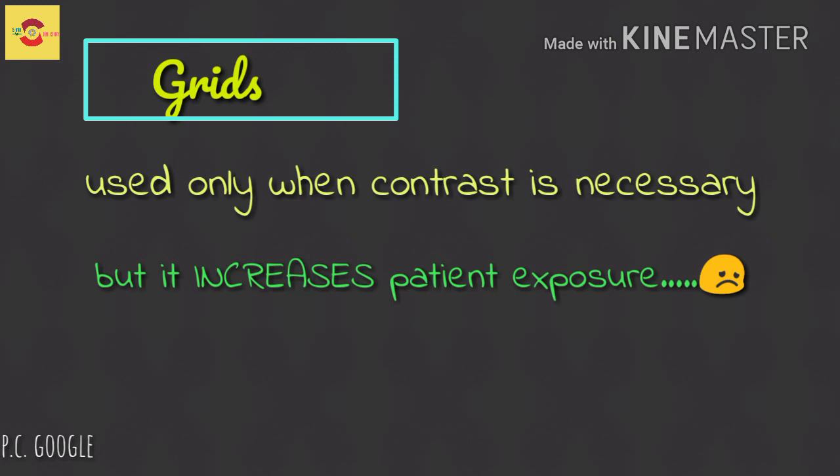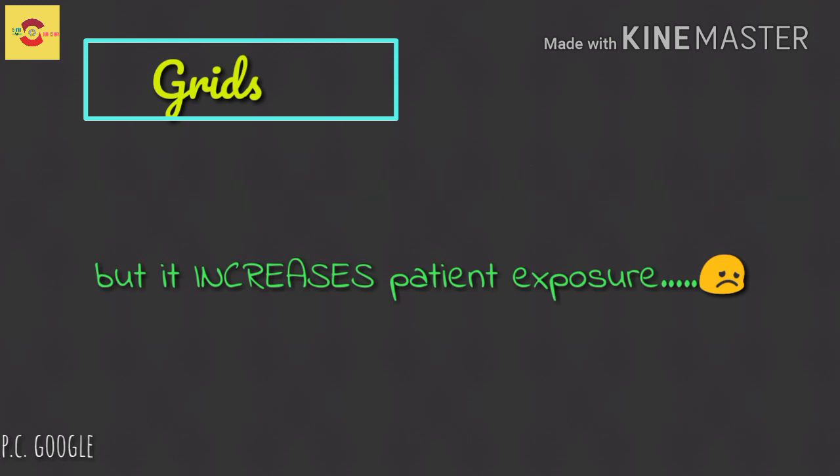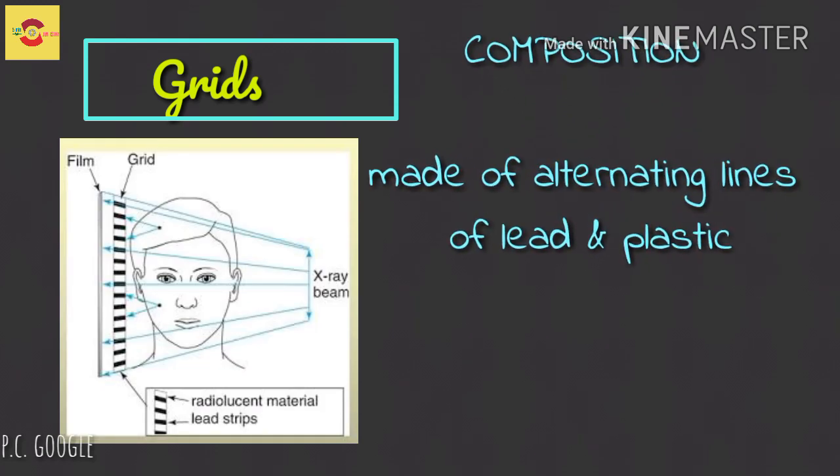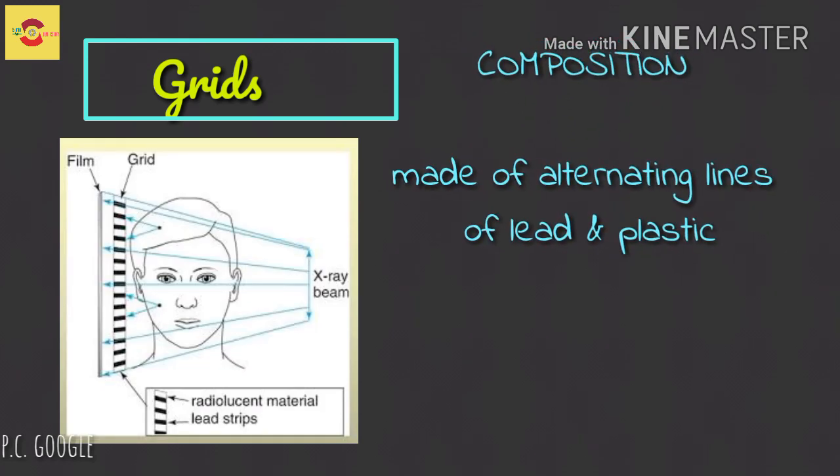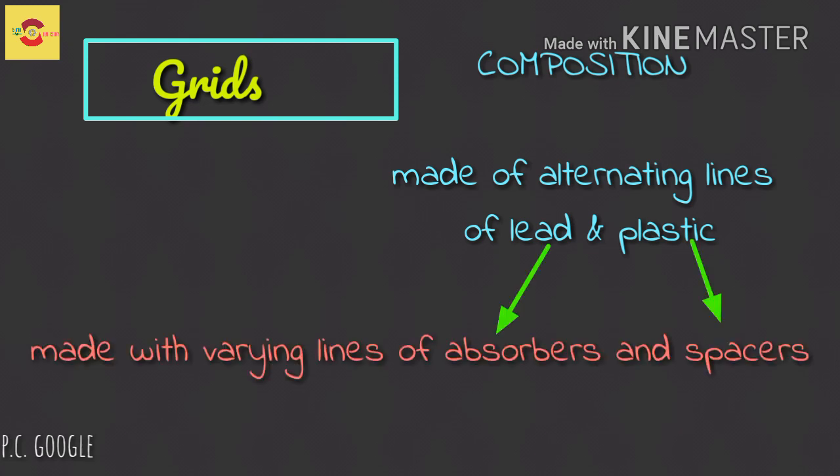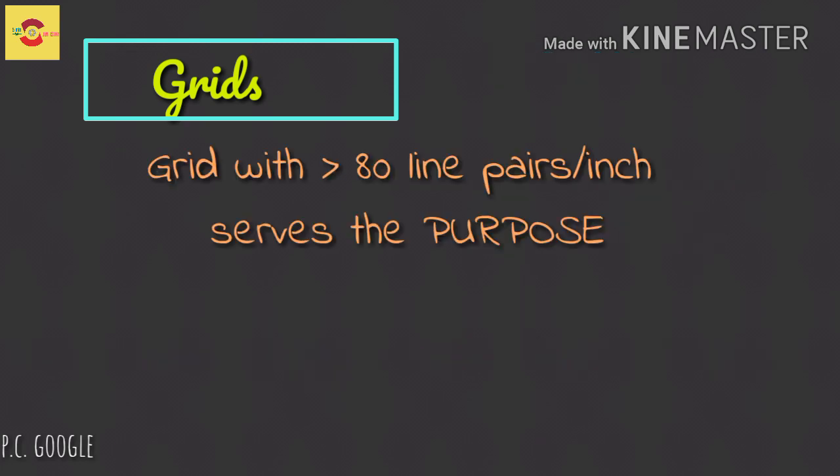What are they composed of? Grids are usually made of alternating strips of lead, which is radiopaque material, and plastic radiolucent material as spacers. Grids are made with varying numbers of pairs of spacer and absorber material for every square inch. Grids with 80 or more line pairs per inch do not show the black grid lines on the resultant image.